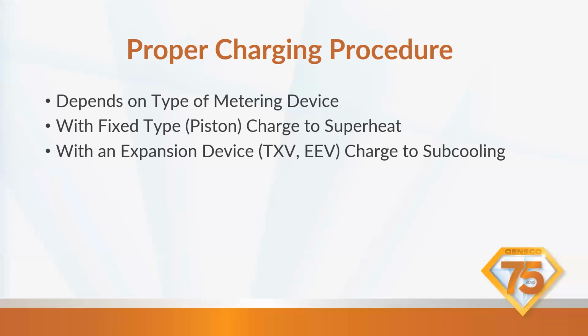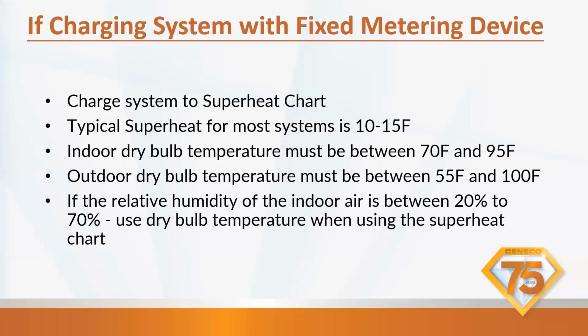And then know what kind of expansion device you have. Do you have a TXV or an EEV? And TXV, it doesn't have sensors on it. Well, it has a sensing bulb. I take that back. And then the EEVs have the liquid line sensor and the gas temperature line sensor, and we're going to charge the subcooling with these devices. If charging a system with a fixed metering device, I just wanted to touch on this because we do have to deal with these a lot with the pistons, and we get calls on them.